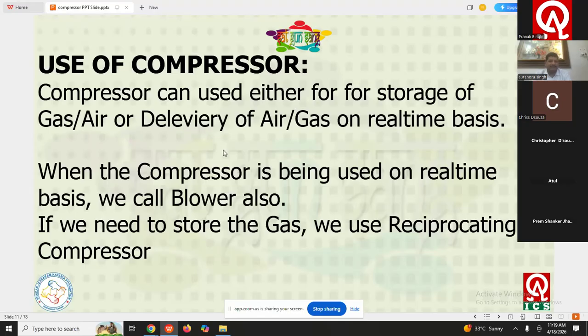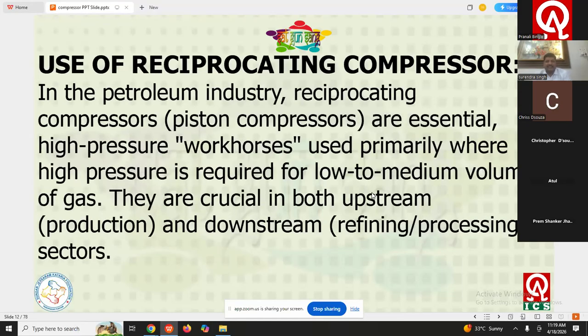Now, use of compressors. A compressor can be used for storage. We saw the air compressor which we use for tire inflation. When the compressor is being used on a real-time basis, we call it a blower, and when we need to store the gas, then we use a reciprocating compressor. Use of the reciprocating compressor in the petroleum industry: this is one good thing about the reciprocating compressor. When we need high pressure and low discharge or low volume, then we use this reciprocating compressor. So when high pressure is required and low to medium volume, meaning the volume is not required in a huge amount, then we require this reciprocating compressor.